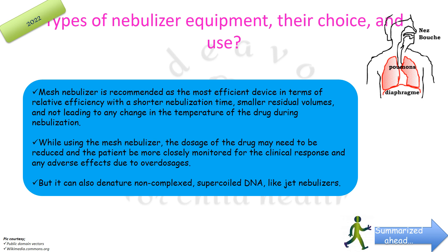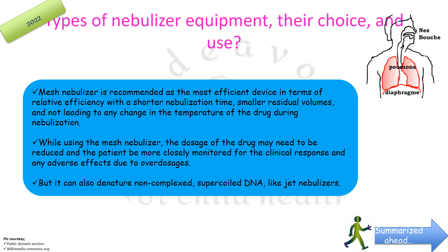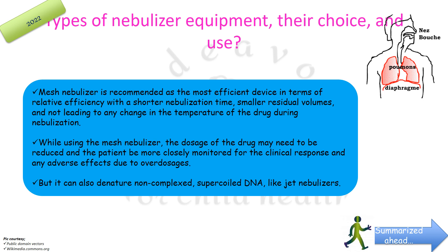The mesh nebulizer is recommended as the most efficient device in terms of relative efficiency, with very short nebulization time, short residual volume, and no change in drug temperature during nebulization. However, when using a mesh nebulizer, the dosage may need to be reduced and the patient monitored more closely for clinical response and adverse effects due to overdosage, given its high efficiency. It can also denature non-complex supercoil DNA, as jet nebulizers do.